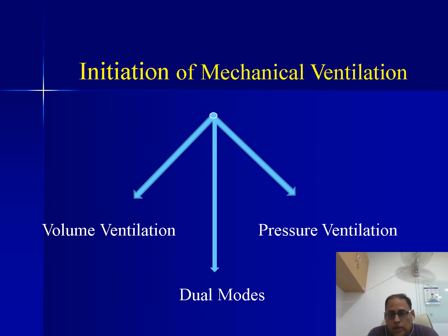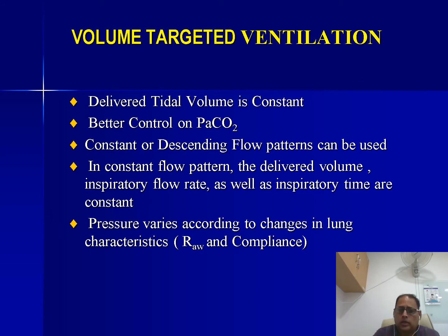Now, as I said earlier, there could be a volume controlled ventilation, there could be a pressure controlled ventilation, and in some cases there could be dual modes of ventilation. Now, if you look at the volume targeted or volume controlled ventilation, you actually give a prefixed tidal volume which is constant, and the patient receives that tidal volume in each breath, and since the tidal volume is guaranteed, you have a better control on the PaCO2 level. But there is a small catch.